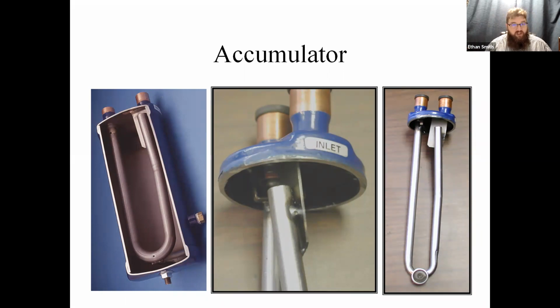So if you've got an accumulator in there and you do a compressor change out, this is another good reason that you should be dumping all the oil out of your old compressor to make sure that you've got oil. I have gone out to accumulators where they have changed the compressor multiple times and the accumulator is completely full of refrigerant oil because it's got 2 or 3 compressors worth of refrigerant oil in that accumulator at that point.